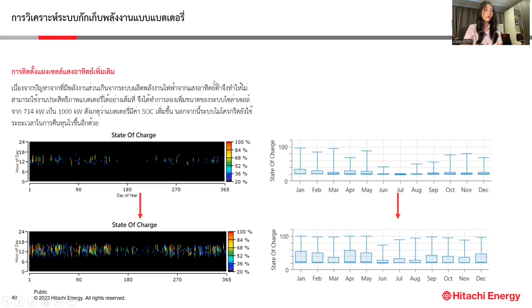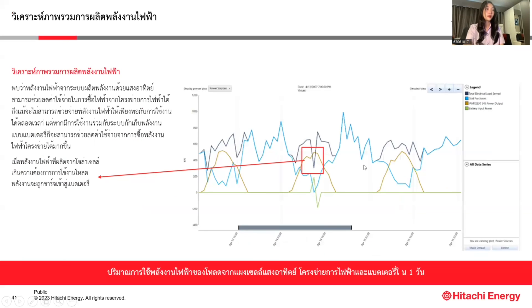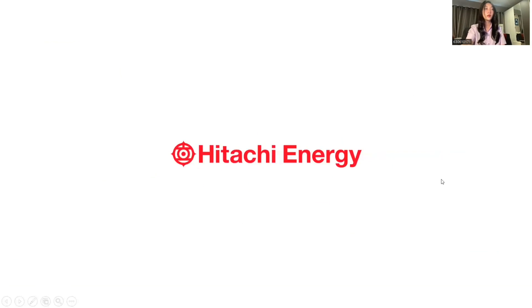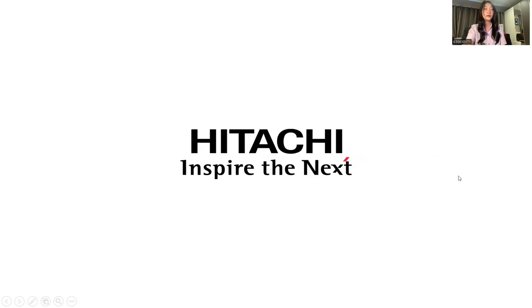Due to the problem of low excess energy production from the solar panel system, the battery system cannot operate efficiently. To address this, we increase the solar panel system's capacity from 714 kW to 1,000 kW, resulting in a higher state of charge (SOC) in the batteries. Additionally, the microgrid system achieves a shorter payback period. In summary, the solar panel system helps reduce electricity production costs, even though it doesn't always supply electrical energy to the loads. However, when integrated with the battery storage system, it can significantly improve electricity production efficiency. This concludes the presentation. Thank you for your attention.